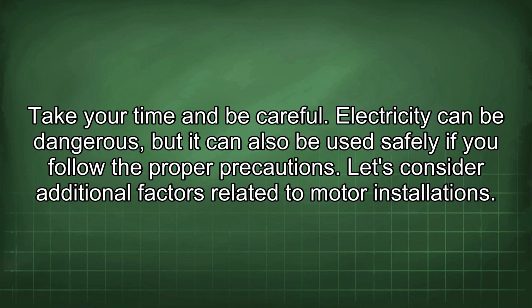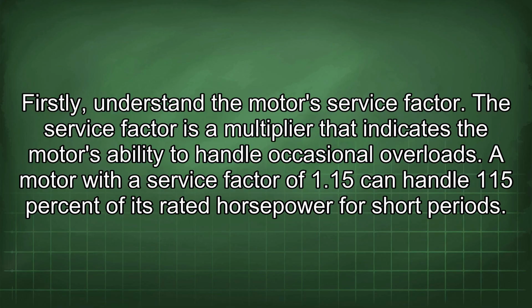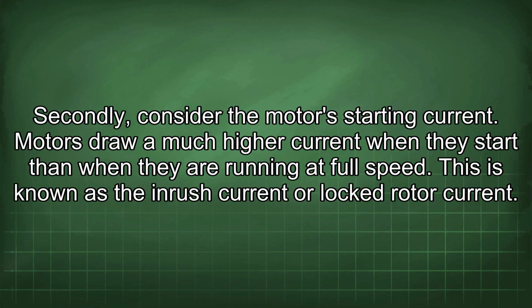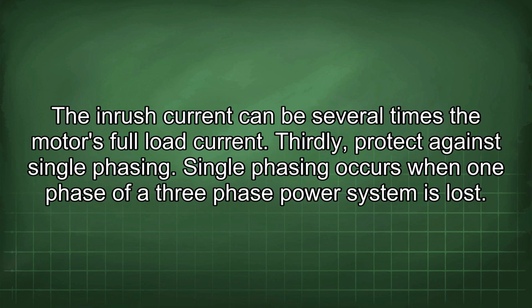precautions. Let's consider additional factors related to motor installations. Firstly, understand the motor's service factor. The service factor is a multiplier that indicates the motor's ability to handle occasional overloads. A motor with a service factor of 1.15 can handle 115% of its rated horsepower for short periods. Secondly, consider the motor's starting current. Motors draw a much higher current when they start than when they are running at full speed. This is known as the inrush current or locked rotor current. The inrush current can be several times the motor's full load current.